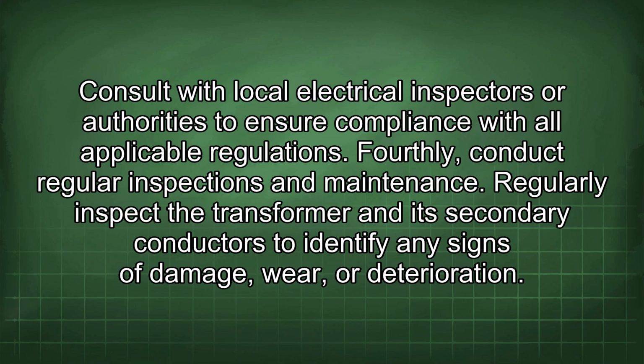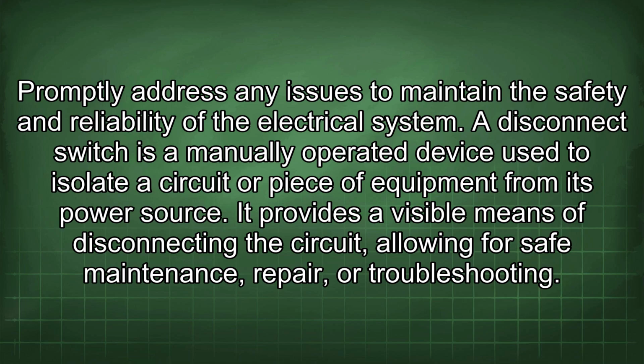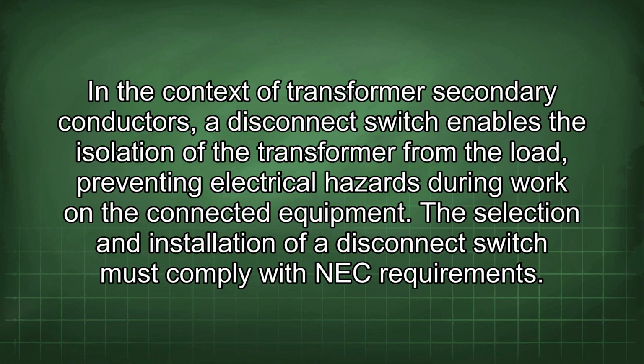Fourthly, conduct regular inspections and maintenance. Regularly inspect the transformer and its secondary conductors to identify any signs of damage, wear, or deterioration. Promptly address any issues to maintain the safety and reliability of the electrical system. A disconnect switch is a manually operated device used to isolate a circuit or piece of equipment from its power source. It provides a visible means of disconnecting the circuit, allowing for safe maintenance, repair, or troubleshooting. In the context of transformer secondary conductors, a disconnect switch enables the isolation of the transformer from the load, preventing electrical hazards during work on the connected equipment.